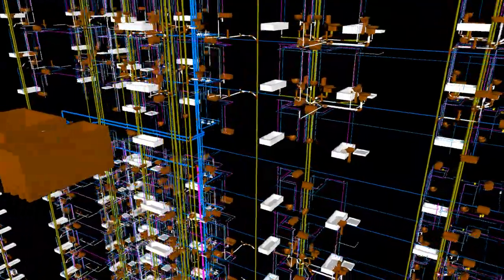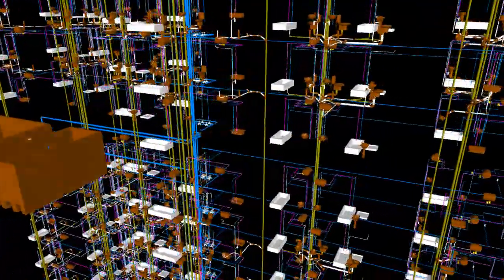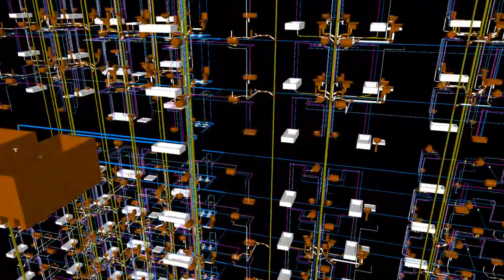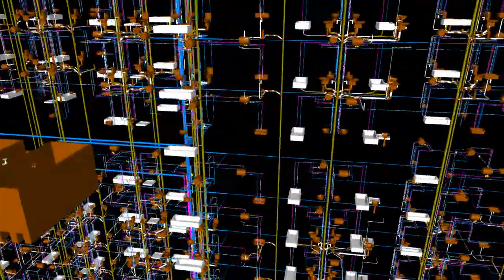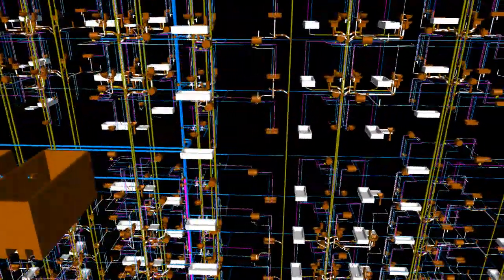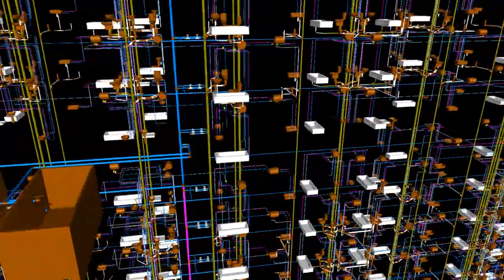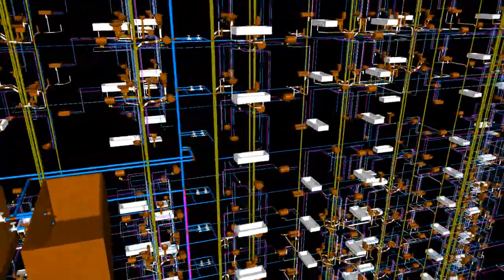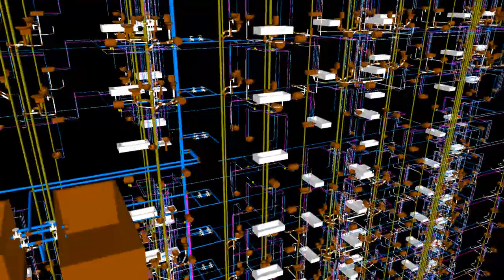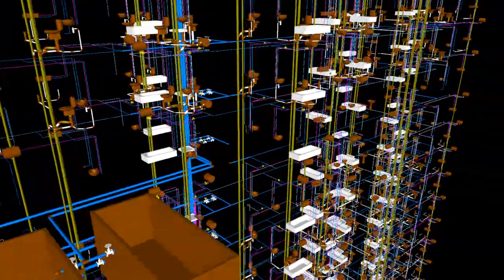Booster pumps shall be provided near the roof water storage tank of each tower to serve the top three floors immediately below the roof level and remaining floors shall be served by gravity.